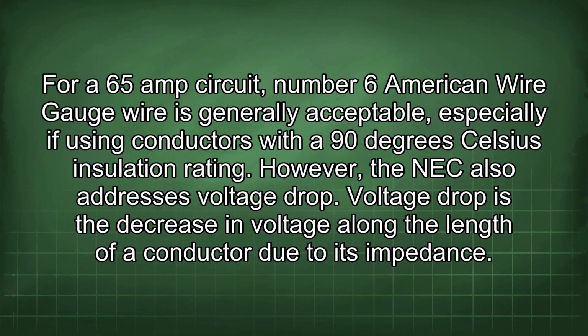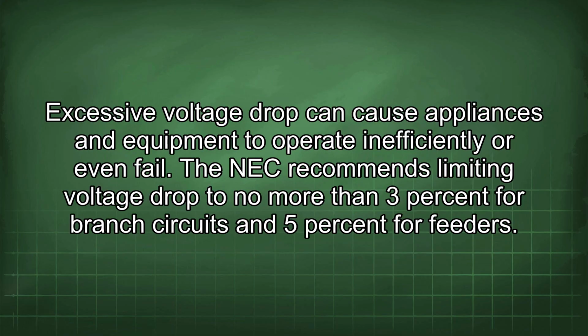However, the NEC also addresses voltage drop. Voltage drop is the decrease in voltage along the length of a conductor due to its impedance. Excessive voltage drop can cause appliances and equipment to operate inefficiently or even fail. The NEC recommends limiting voltage drop to no more than 3% for branch circuits and 5% for feeders.